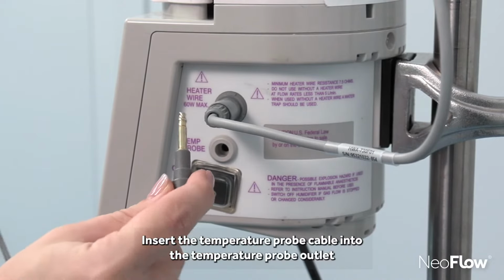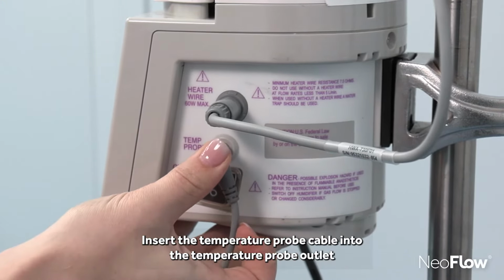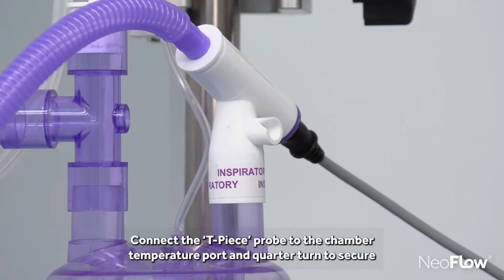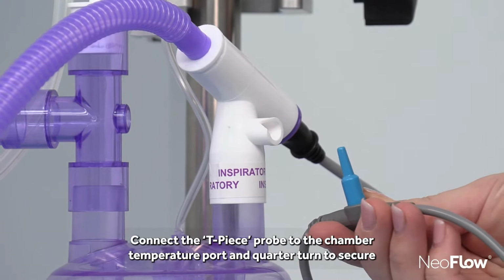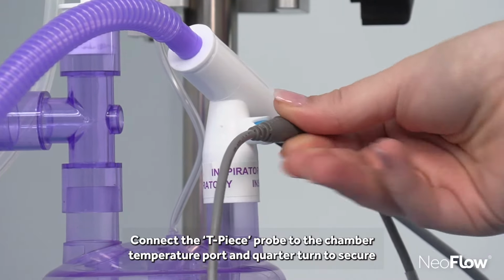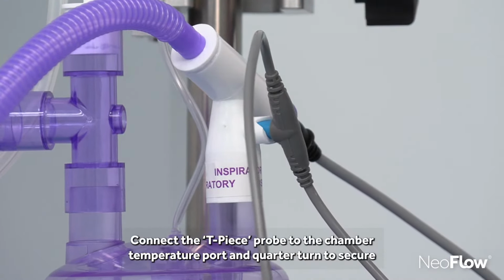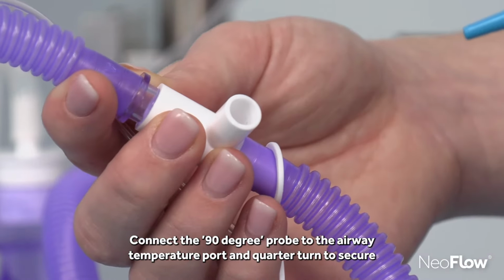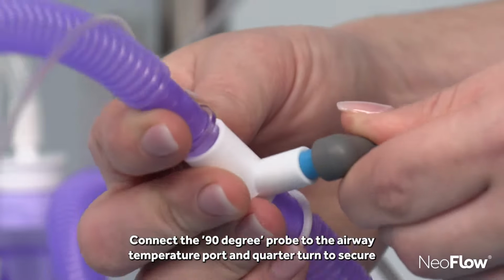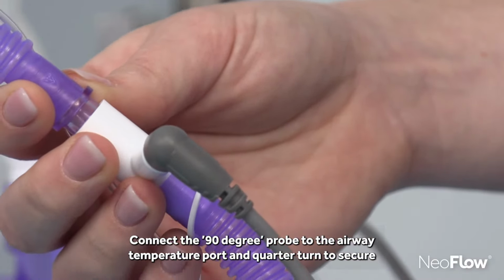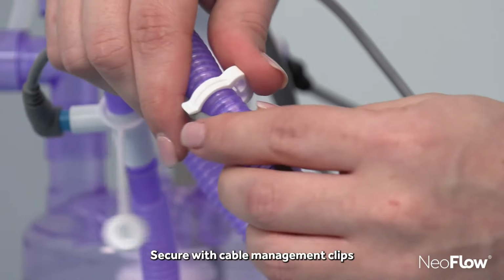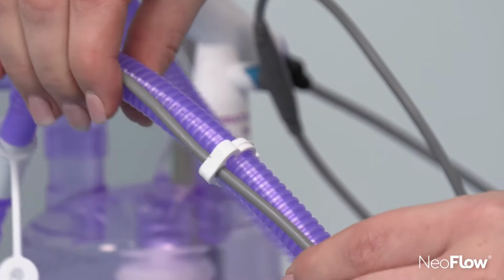Insert the temperature probe cable into the temperature probe outlet. Connect the T-piece probe to the chamber temperature port and quarter turn to secure. Connect the 90-degree probe to the airway temperature port and quarter turn to secure. Secure with cable management clips.